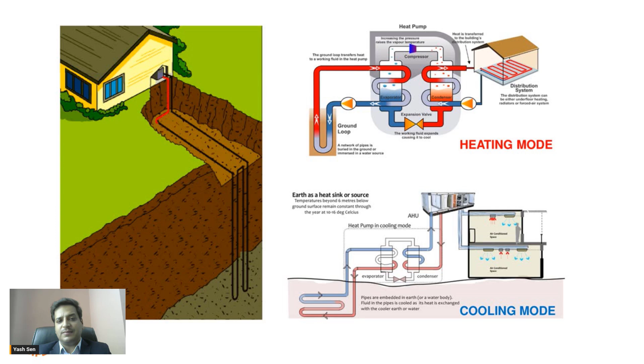So why is it very beneficial to install a geothermal system? Because geothermal systems work at 400 to 500% compared to whatever conventional HVAC systems we have right now, whether VRF systems, splits, water cooled chillers, or air cooled chillers. This is the technology having the most optimum and highest COP energy levels. You can see that we are getting 3 to 4 units of free energy. This is an average, but in some countries and installations we get even more. So basically, if we give 1 unit of energy or electricity to the ground source heat pump, we can easily get 4 to 5 units of thermal heat.